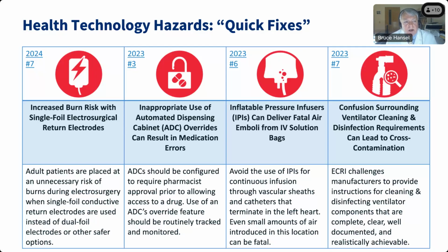Those are inflatable bags that have a pocket in which you put an IV bag, and then you can pump this pocket up to squeeze the solution out of the IV bag. The unfortunate thing is most IV bags come with air in them, and you can squeeze that air into the patient under some circumstances, in which you can have a lethal outcome there.